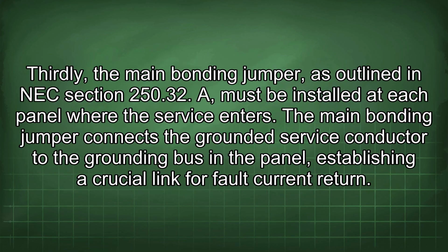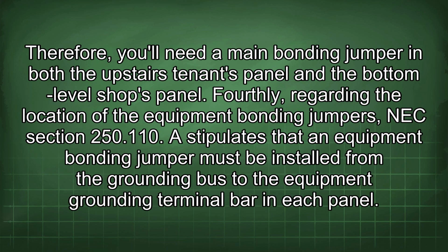Thirdly, the main bonding jumper, as outlined in NEC section 250.32(A), must be installed at each panel where the service enters. The main bonding jumper connects the grounded service conductor to the grounding bus in the panel, establishing a crucial link for fault current return. Therefore, you'll need a main bonding jumper in both the upstairs tenants panel and the bottom level shops panel.